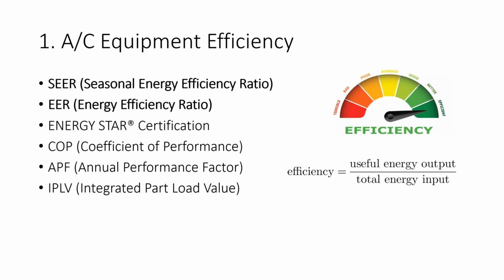Air conditioning efficiency can be described and explained in a number of different ways. Here is a list of systems and units we use: SEER, seasonal energy efficiency ratio; EER, energy efficiency ratio; the Energy Star certification process; COP, coefficient of performance; APF, annual performance factor; and IPLV, integrated part load value. All of these tell us about efficiency, and efficiency is basically the ratio between the output energy or work done and the input power or energy.